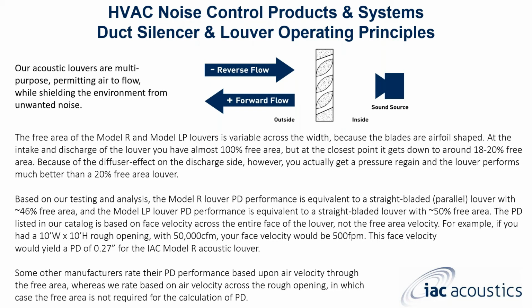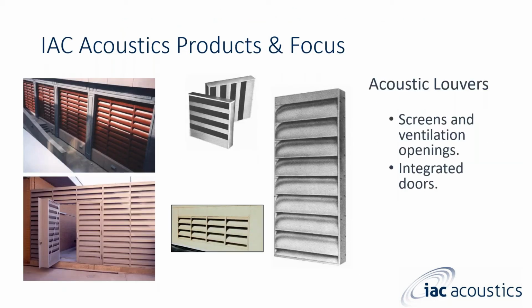Design to performance first. Free area will end up being what it is. I will say this also, that when you design a free open area versus performance, if a 10-foot by 10-foot rough opening is designed to performance first, and then free area is what it is, say at 46%, you want to make it 50%, literally you're going to have to make that hole probably 12 feet by 12 feet. So that's kind of what happens, the difference between free area and performance.